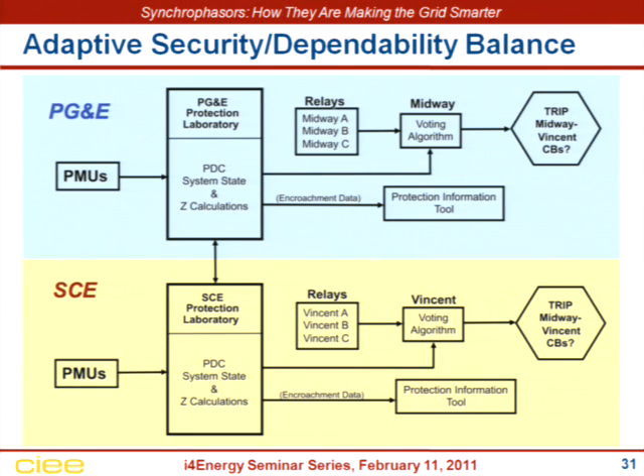It's redundancy. However, when the system is stressed, in other words, lines out of service, things are happening that are sort of the impending signs of a blackout, then the relays have a much higher probability of tripping falsely. And then if they do that, they contribute to a blackout. So what the PMU data does and what the algorithm that's in here does is it detects when the system is in this stress state by bringing in all this wide area data. And when that happens, and it detects those conditions, it sends a signal over here and says, institute this voting algorithm now. And it puts it in place.